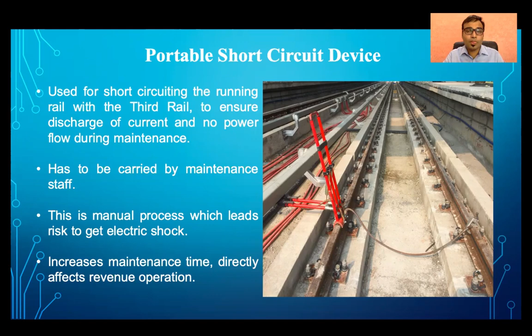So to overcome these issues in Kanpur Metro, we are using an automatic earthing and short circuit device. These are fixed devices which are installed in the panels at each substation, and they are connected through cables to the main line. Since it is a motorized device, it can be operated remotely through SCADA, which is the supervisory control and data acquisition system. It is very easy to operate.